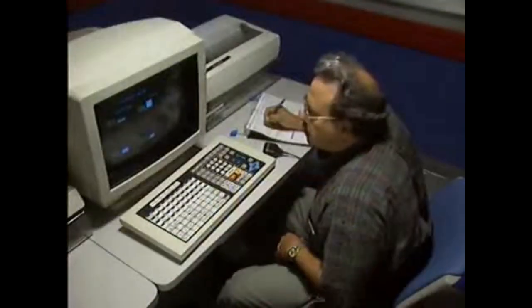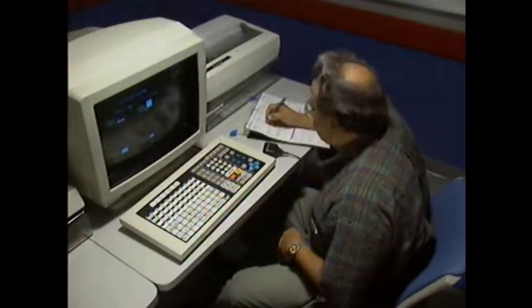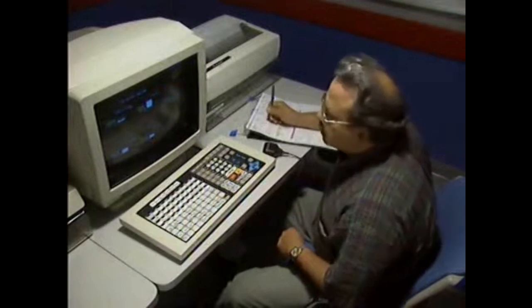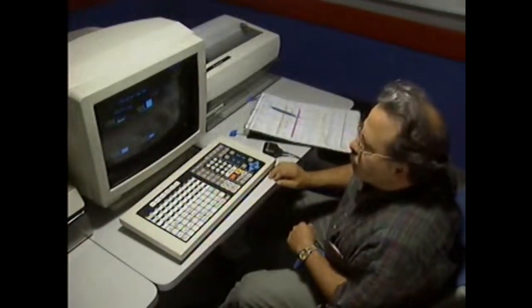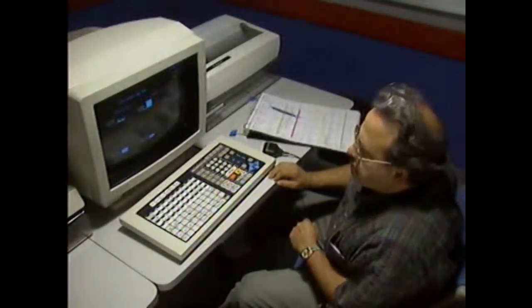The outside operator reports that the transfer pump appears to be operating properly. The control room operator records in the log that the transfer pump has been properly started. After logging the start of the pump, the control room operator again checks the indicators. This time, he finds that the level indicator for the process feed tank is not indicating any level in the tank. At this point, the operator suspects a problem.